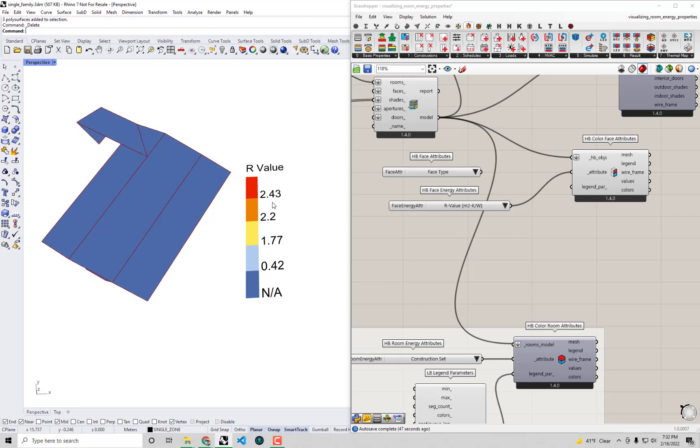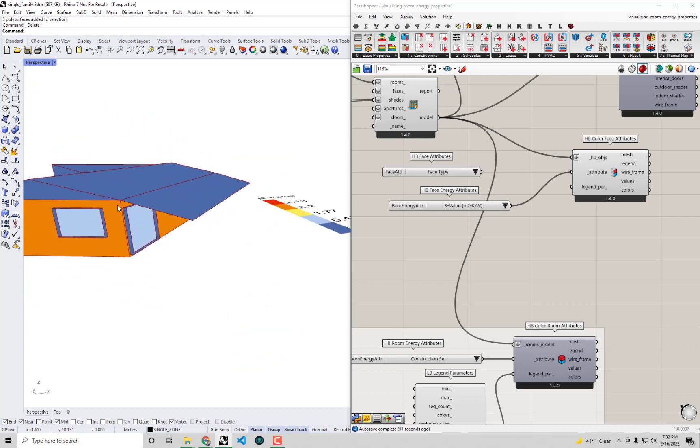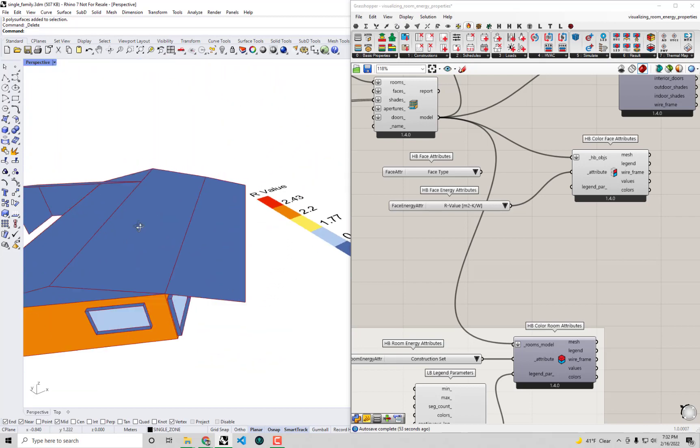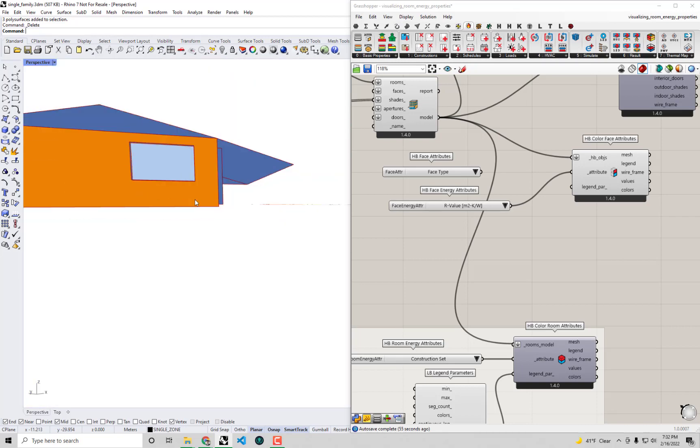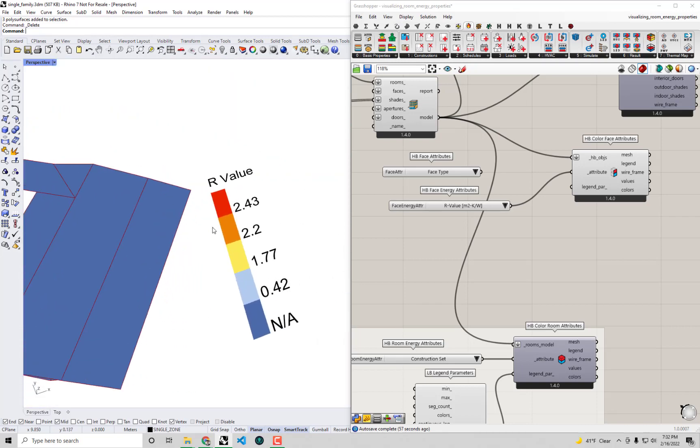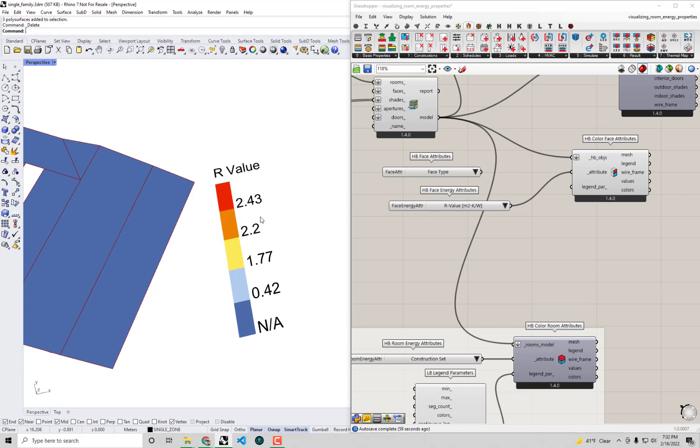You can see the maximum R value of what looks like it's probably the roof has the highest R value. If I were to go inside there, yeah that's red. You can see that has an R value of 2.43 in metric or that would be about 10 or 11 or so I think within IP.